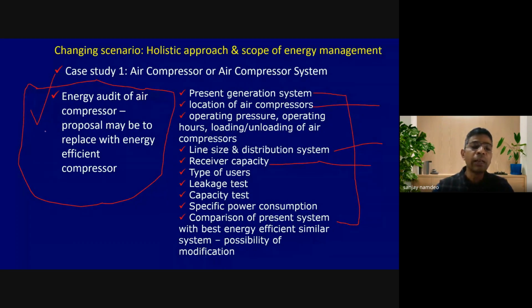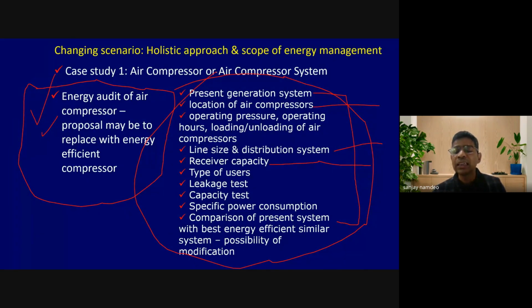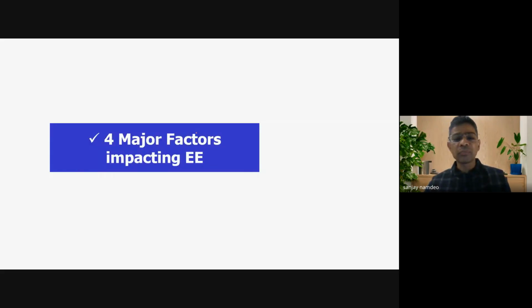So it means just by replacing the old equipment with the new equipment, or the inefficient equipment with the efficient equipment, will not serve the purpose. We need to go into the micro details of all these factors by proper study, and then identify gaps: whether my line sizes are proper or not, whether my receiver location is proper or not, whether the receiver is put at appropriate places or not, what is my leakage level, what is the loading and unloading pattern of my compressor, what is the consumption pattern of my compressor. All these factors influence the energy performance. So just by replacing old with the new one will not serve the purpose, right?